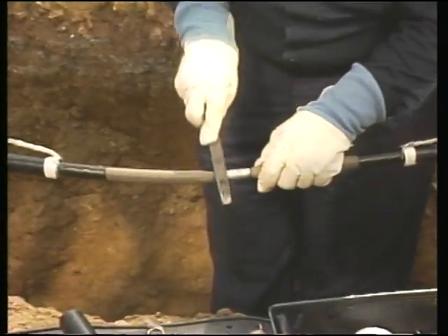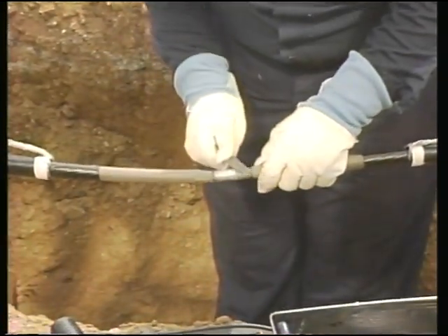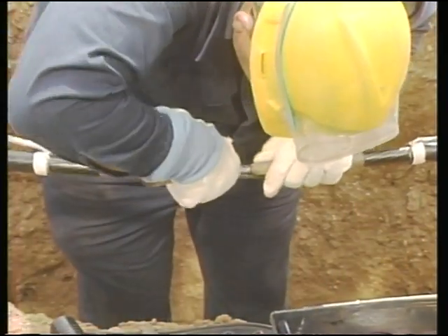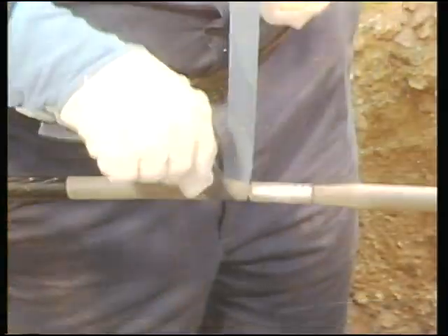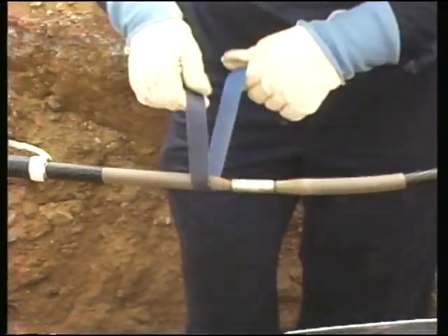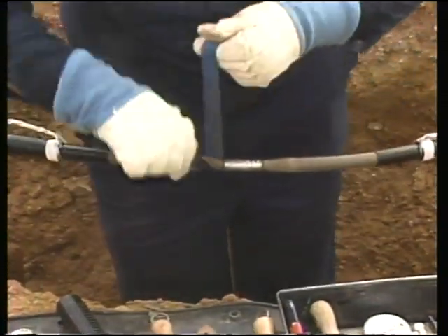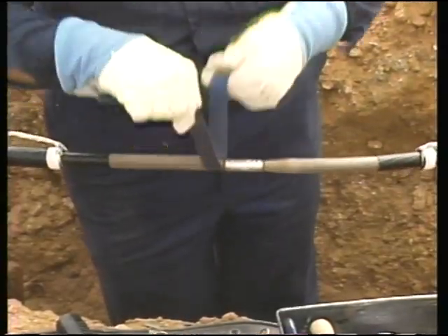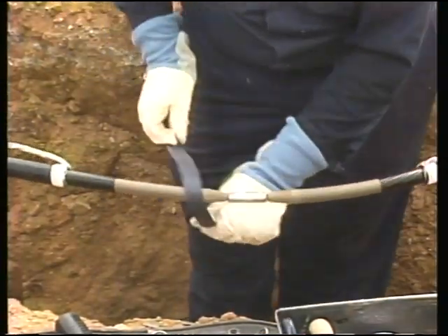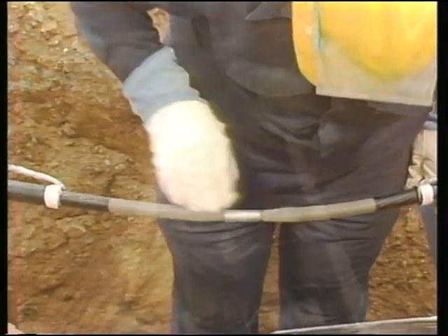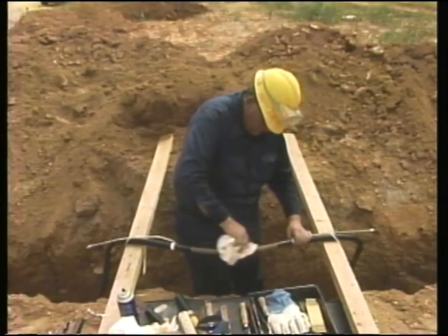Now, after the connector is compressed into place, the workman uses a file to smooth any sharp edges that may have been created from the pressing process. Next, the penciled cable insulation has to be smoothed out, and all traces of semiconductive material must be removed. An approved solvent and non-conductive abrasive cloth or sandpaper may be used for this. Then the connector is wiped clean of any metal shavings or particles.